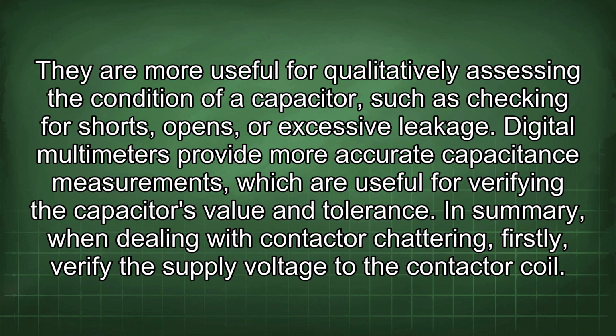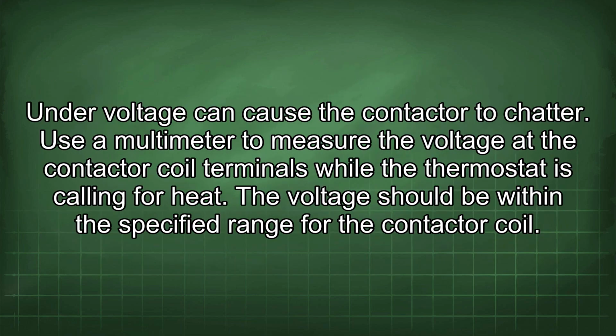In summary, when dealing with contactor chattering, firstly, verify the supply voltage to the contactor coil. Undervoltage can cause the contactor to chatter. Use a multimeter to measure the voltage at the contactor coil terminals while the thermostat is calling for heat. The voltage should be within the specified range for the contactor coil.